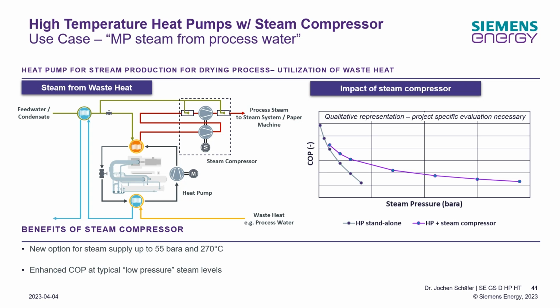We can produce 1.5 bar, for instance, and then have a subsequent steam compression. Doing so, you can see here the line with the steam compression shows an advantage with respect to the coefficient of performance, which can be interesting. So in part we can base the decision on techno-economics: is it better to have only the high temperature heat pump, or the combination of a high temperature heat pump plus a steam compressor?